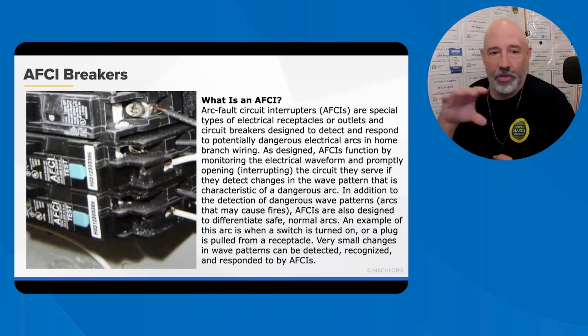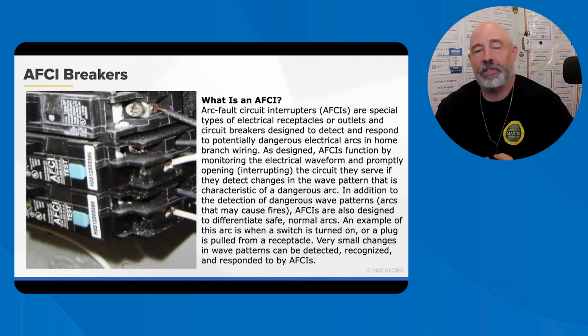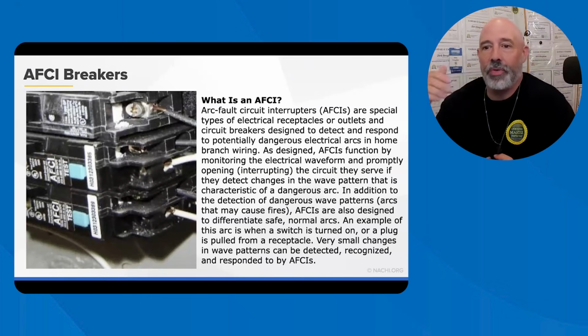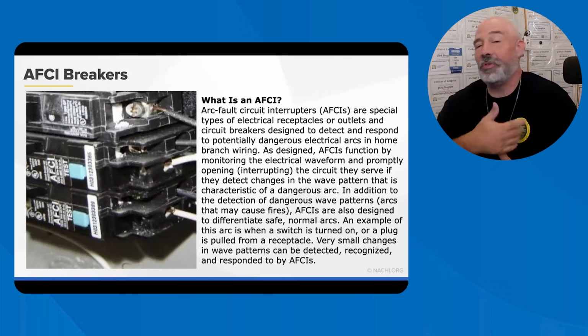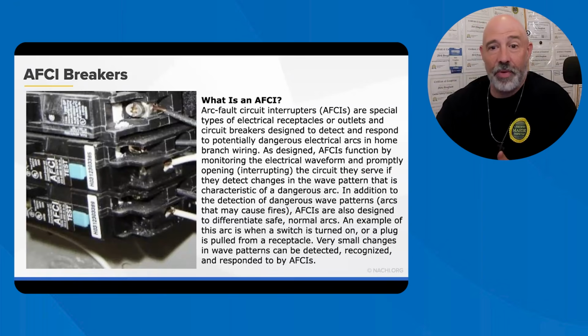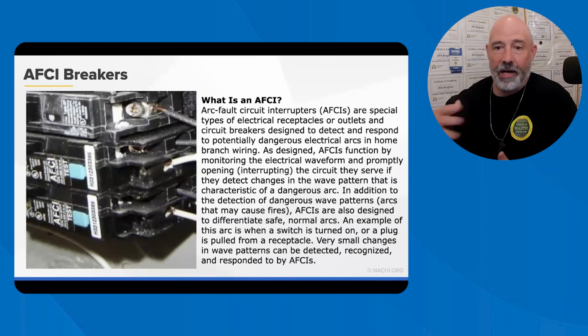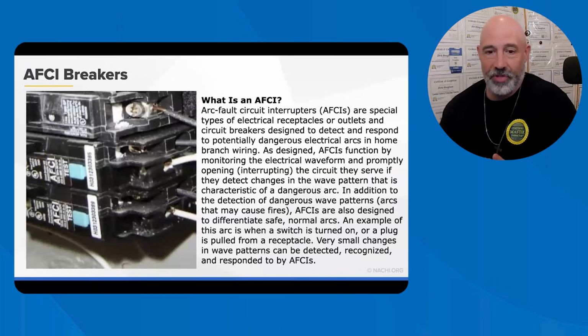So here's a brief history. In 1999, under the NEC, these breakers were required only on bedroom receptacles. In 2002, they expanded to all the 15 amp and 20 amp circuits, single phase, of course. Later on, they developed into including hallways and similar rooms. And now it's pretty common to just see AFCIs on every single one of them. Again, they need to be exercised. So make sure that you tell your customers to exercise these at least twice a year. Just trip them, make sure that they're working.